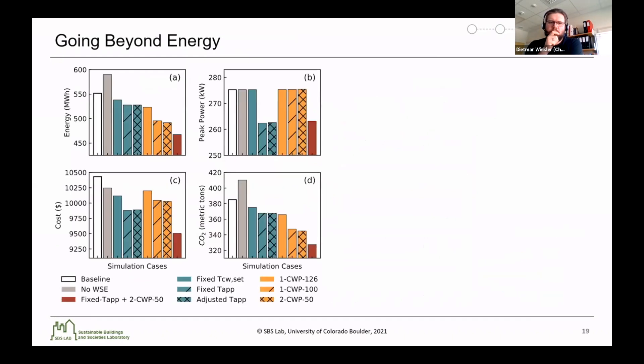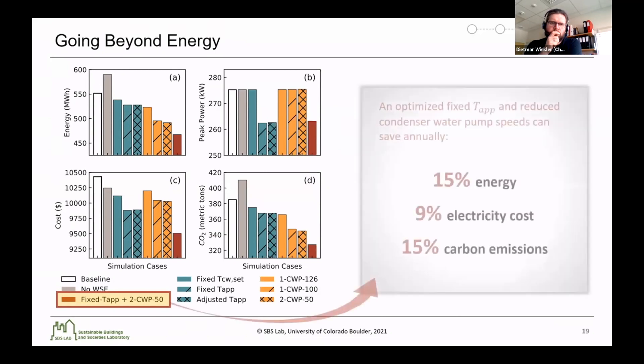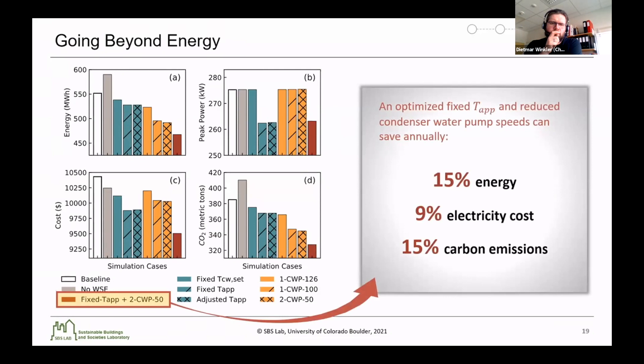Going beyond energy, we also evaluated energy costs and carbon dioxide emissions, because energy alone is more of a means to an end, where cost and carbon emissions are the end products and impacts that communities see. For these case studies, the combination of the fixed approach temperature and the two condenser water pumps operating at 50 kilograms per second produced the best results: saving 15% of energy, 9% on electricity costs, and 15% on carbon emissions.